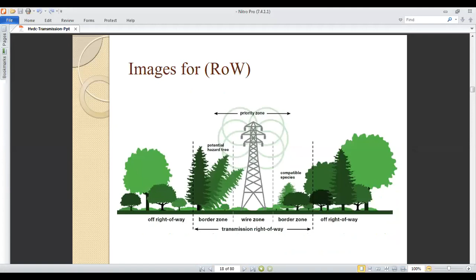Next is the comparison of right of way for AC and DC lines. Suppose in the case of a 400 kV AC line, the right of way is 96 meters. But in the case of a plus-minus 500 kV DC line, we require less right of way, that is 46 meters. So we can see that in the case of DC, the right of way is very small. We need a small area for a DC line.